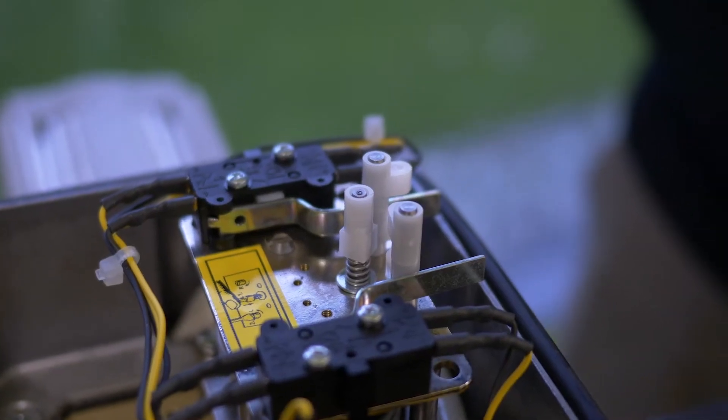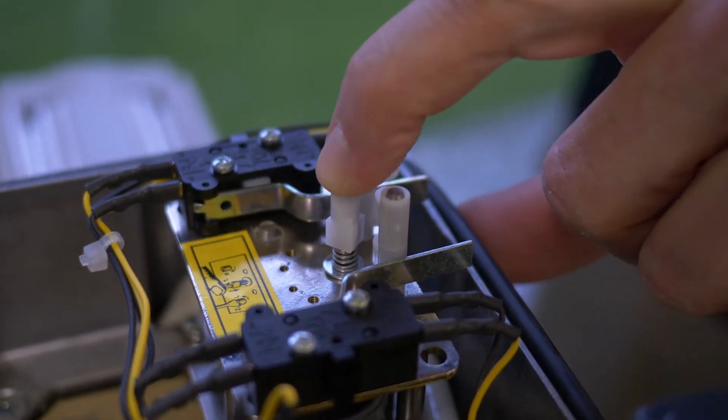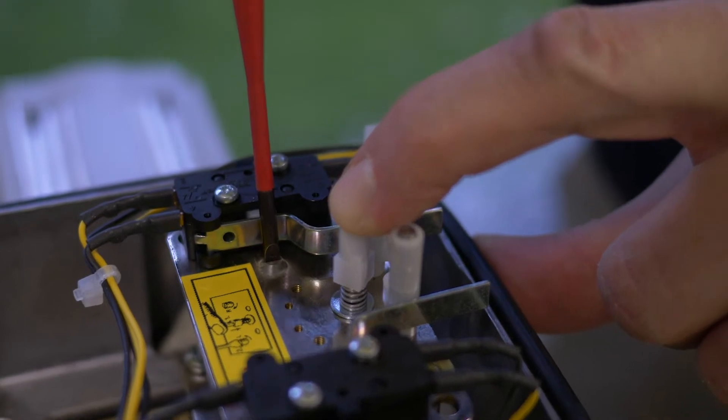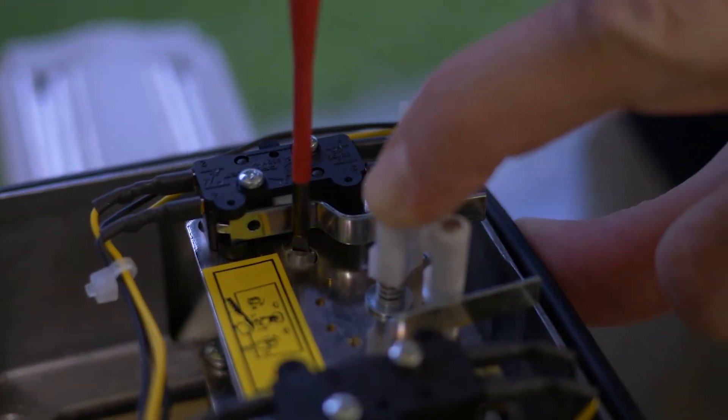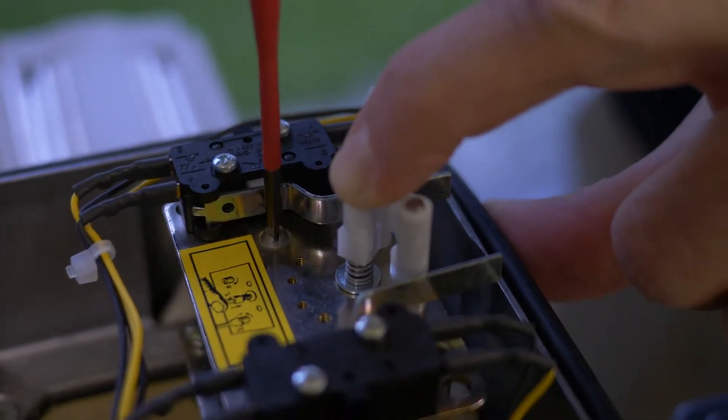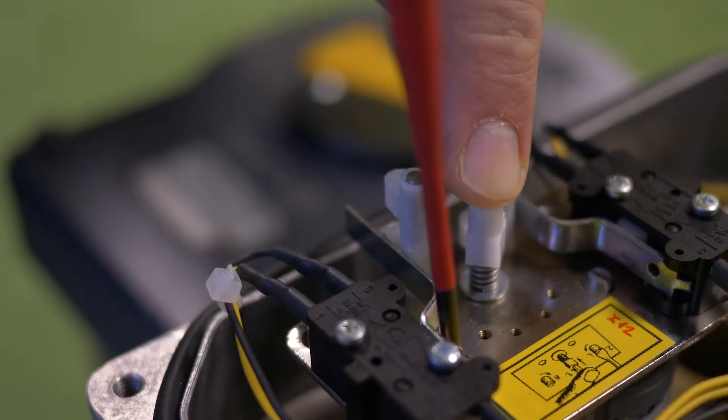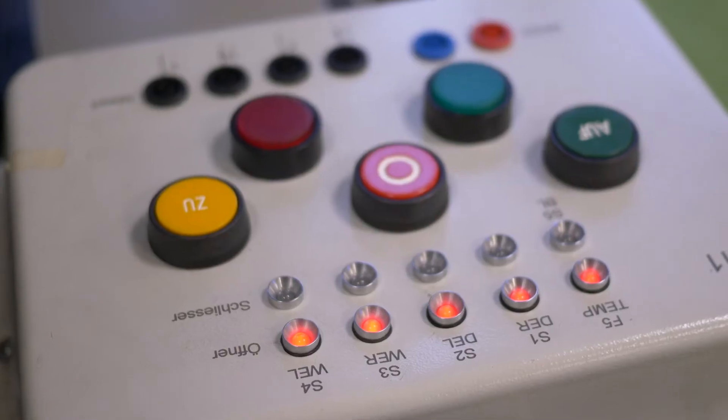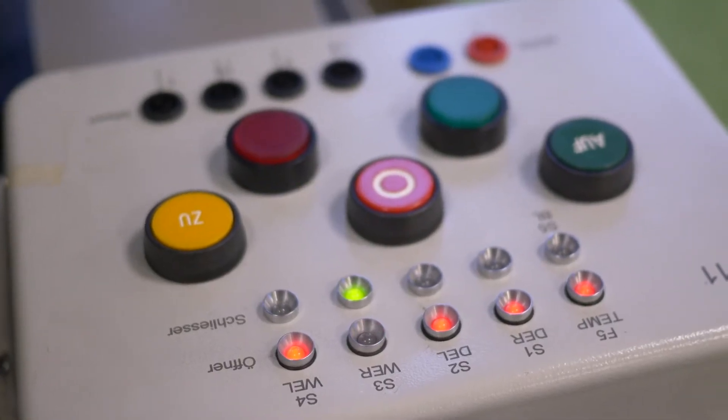To set the close end limit switch, press the white cam and insert the screwdriver on the screw and turn as shown on the yellow label till the switch is pressed. Then release the white cam and check if it's fixed.